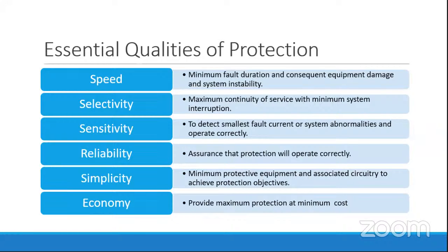So the cost of the protective systems should be balanced against the risk involved if protection is not sufficient and there is not enough redundancy. The primary objective of the relay is to protect its particular zone, so that it operates primarily first. But if some protection fails, then we need to have some kind of backup, in a selective way, such that it should operate if any switchgear malfunctions or if it didn't detect the fault in the network.